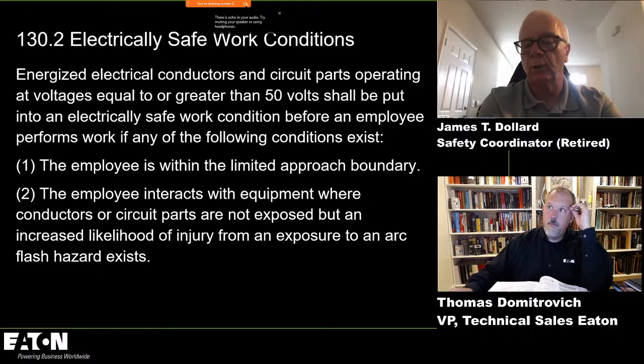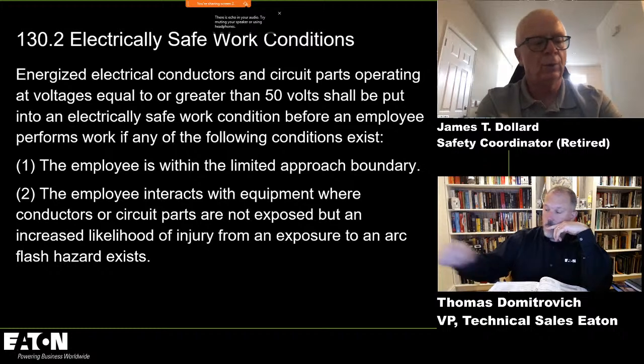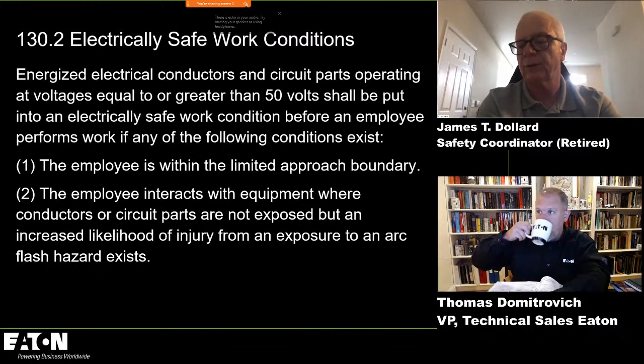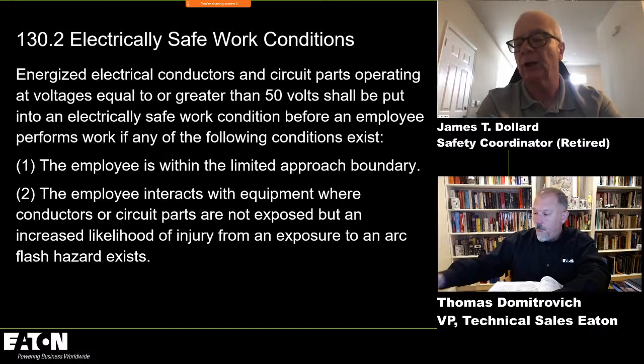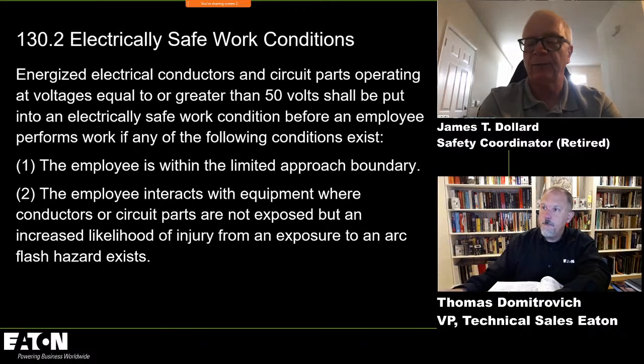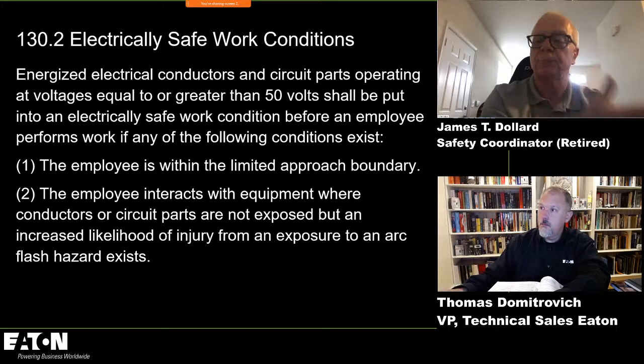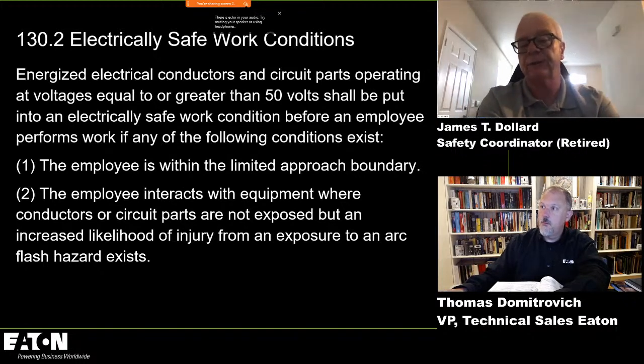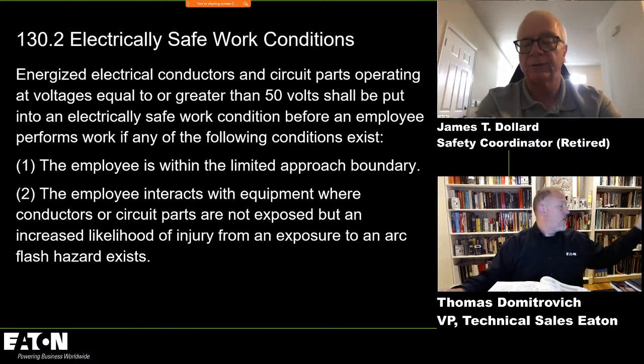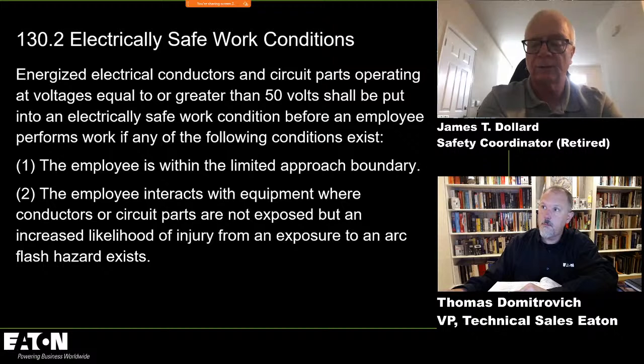And what we do up front in the definition of arc flash hazard is we provide two informational notes. Informational note number one very clearly lays out when you have an arc flash hazard, which is when you have exposed energized conductors or circuit parts, which is easy, or you're interacting in a manner that increases the likelihood. And the second informational note sends you to the likelihood table. It sends you to table 130.5c, and we list all of the tasks where you would be interacting with equipment in a manner that increases that likelihood.